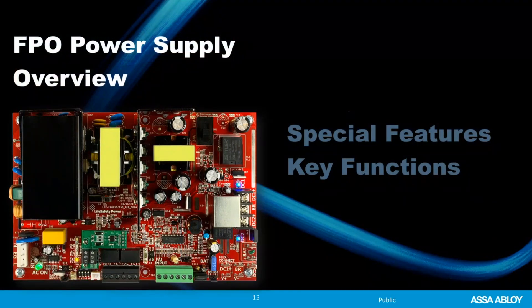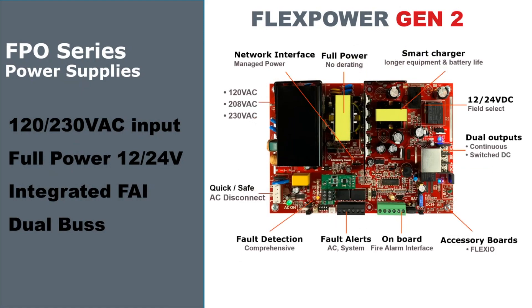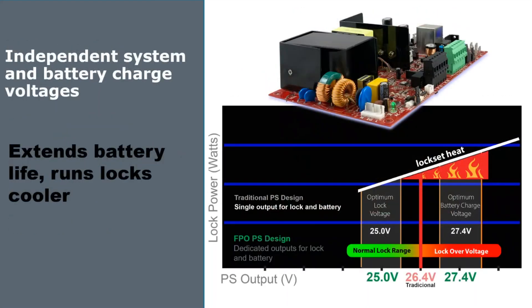The FPO power supply boards are the main power supplies in a life safety power system. There are three power levels available: a 75-watt, 150-watt, and a 250-watt. We rate these in wattage because you get double the current at 12 volts versus 24 volts, so typically a 12-volt device will draw twice as much current as a 24-volt device. This gives you a pretty consistent power system no matter which voltage you're using. No matter which of the three power supply boards you use, they all have the same features and everything is in roughly the same general location. Once you know one, you should know them all.